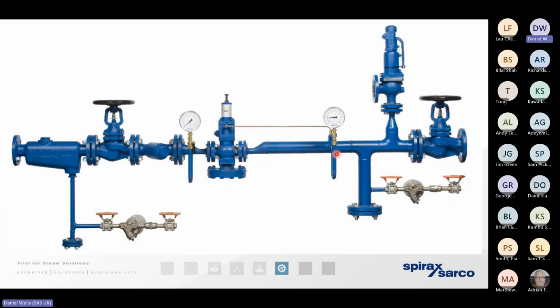We've got a pressure gauge either side of the pressure reducing station, so we can identify when it goes into fault, and we can use it for commissioning purposes. We've got an eccentric reducer coming in and out of the pressure reducing valve, so we're not trapping any condensate. We've got another steam trapping station ahead of that final isolation valve, so we can ensure that by removing the condensate, we're not resulting in a water hammer issue if and when we're going to open that valve. And then finally, we've got a safety valve.